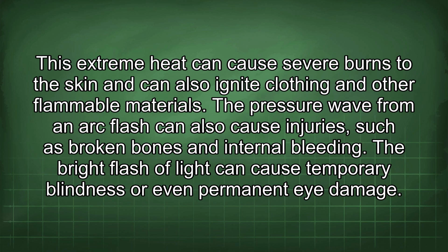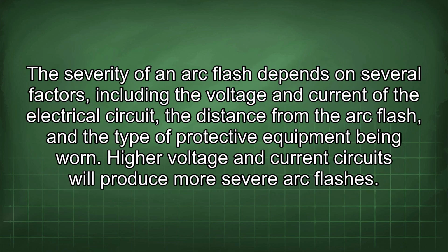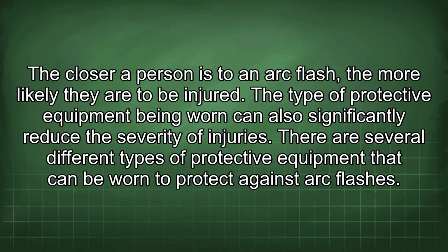other flammable materials. The pressure wave from an arc flash can also cause injuries such as broken bones and internal bleeding. The bright flash of light can cause temporary blindness or even permanent eye damage. The severity of an arc flash depends on several factors, including the voltage and current of the electrical circuit, the distance from the arc flash, and the type of protective equipment being worn. Higher voltage and current circuits will produce more severe arc flashes. The closer a person is to an arc flash, the more likely they are to be injured. The type of protective equipment being worn can also significantly reduce the severity of injuries.